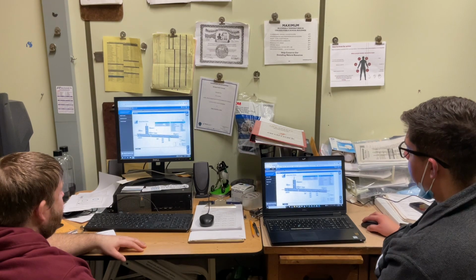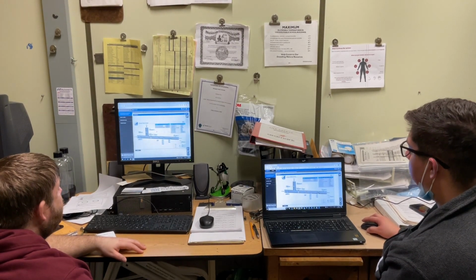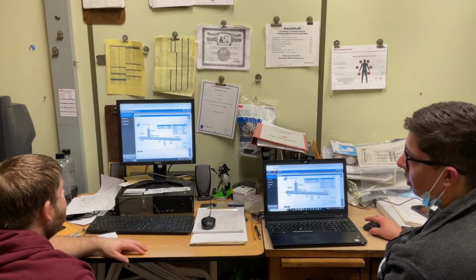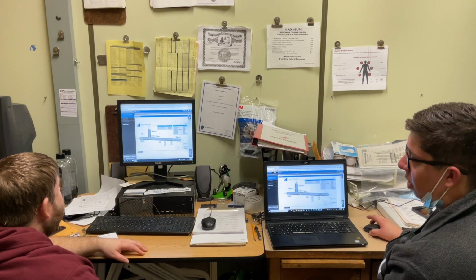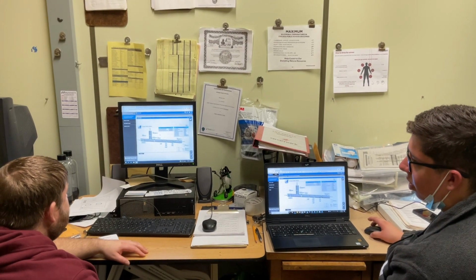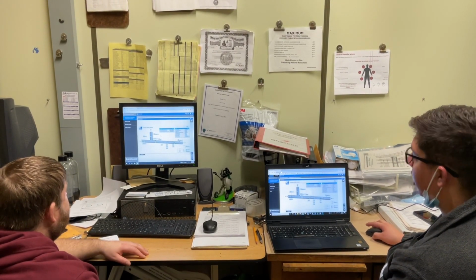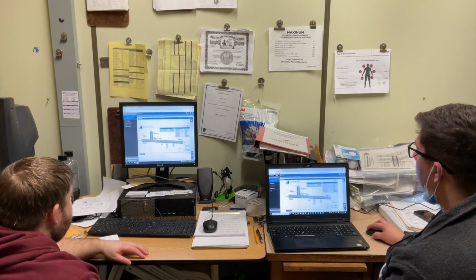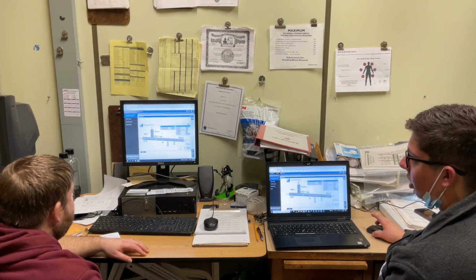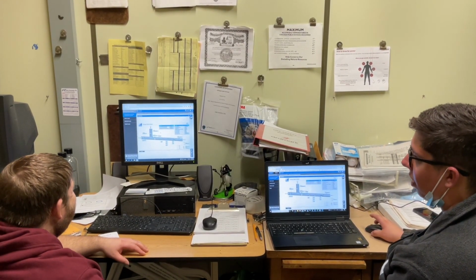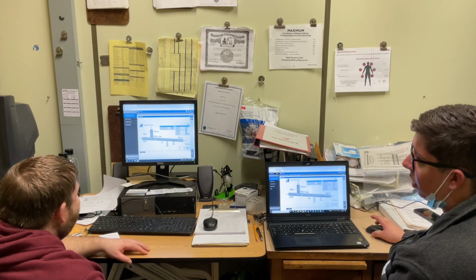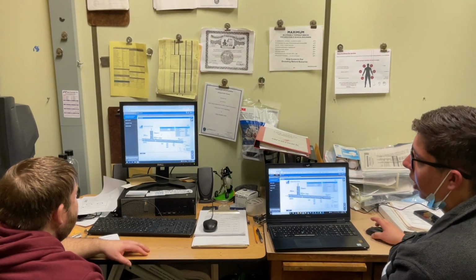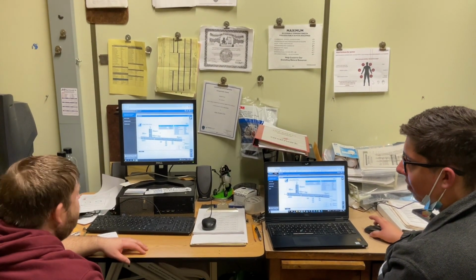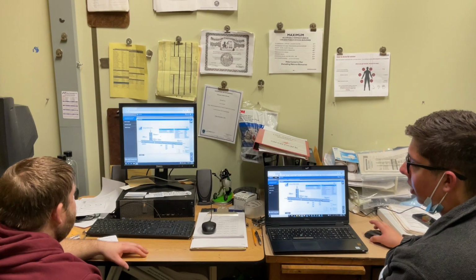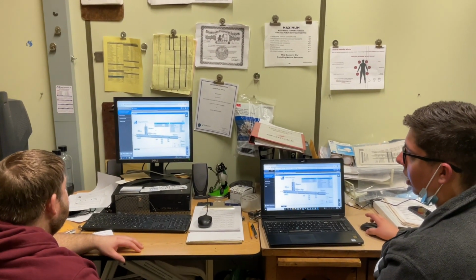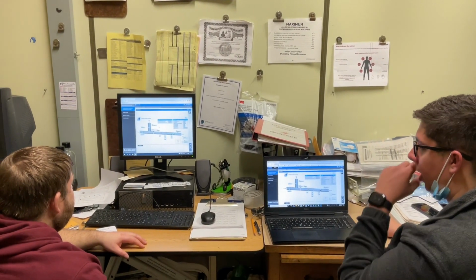You have your return air temp, the pre-filter differential pressure transducer. There's alarms on those points too, so once they start to get dirty, they'll usually go up above that point, and then you'll see that. You've already dealt with the low temperature alarm. That is just like a software point, just to protect the cooling coil, because really it's electric reheat, so that'd be fine, but you really want to protect that refrigerant from the condensing units.